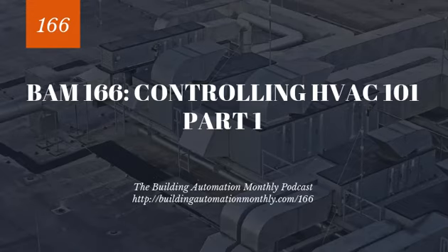It lowers the airflow when it wants to raise the temperature, and it raises the airflow when it wants to lower the temperature. Sometimes you'll have electric heat or hydronic heat in the VAV box, and in that case, you'll tend to control to a heating CFM. The reason is that you want to maintain a certain amount of airflow across the coil so that you maximize heat transfer. If you put too much airflow, you're not going to get the best heat transfer, and if you do too little airflow, you're not going to get the best heat transfer. So there's often a heating CFM, and that's what's going on in these VAV boxes.